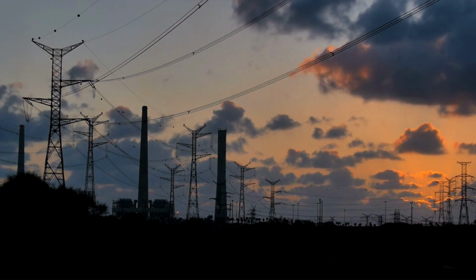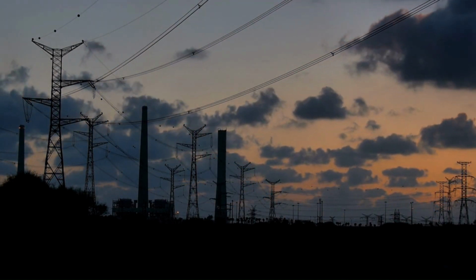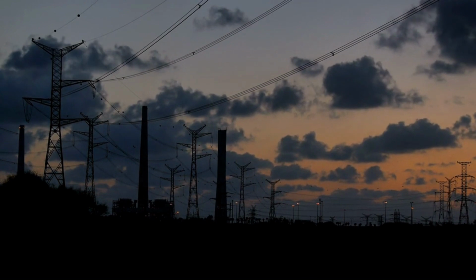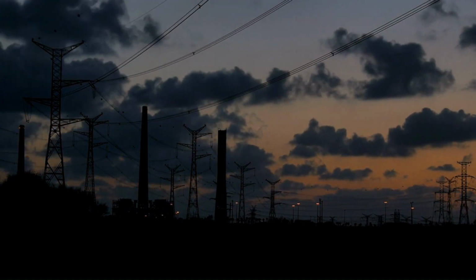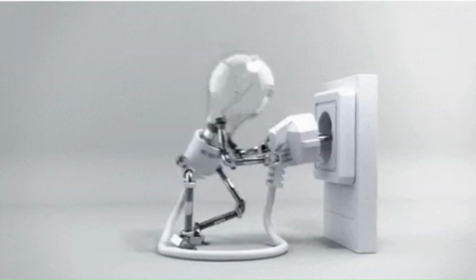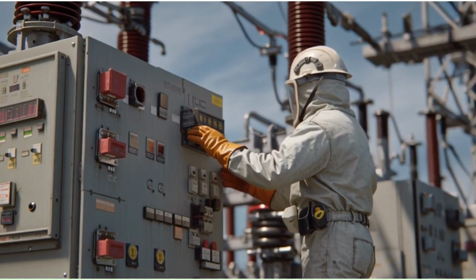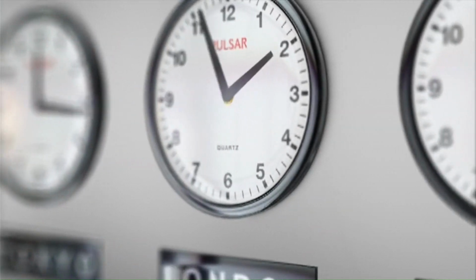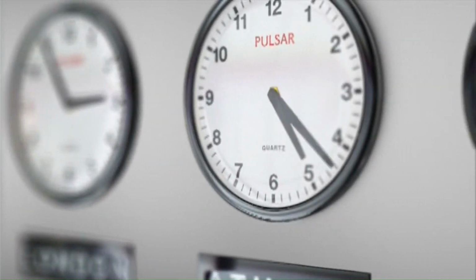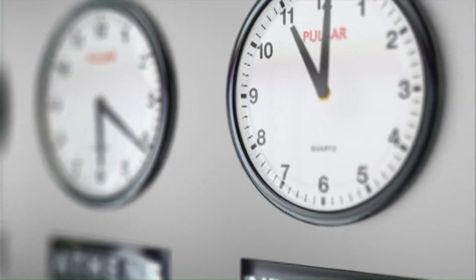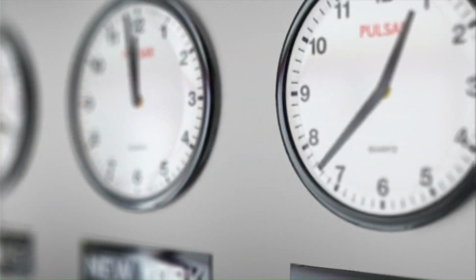Extra high voltage transmission lines transmit a huge amount of electric power. Therefore, it is always desirable that the continuation of power flow through the lines should not be interrupted for a long time. There may be a temporary or permanent fault in the lines. It is normal practice by the operators that after each tripping of the line, they close the circuit breaker. Since these lines carry so much power, any delay in manual reclosing can cause significant loss in cost and stability.